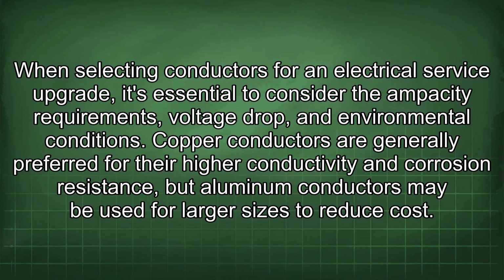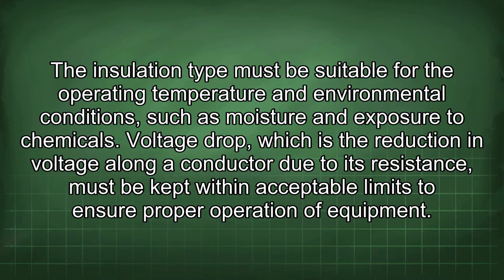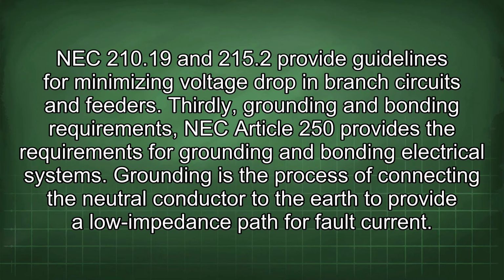Copper conductors are generally preferred for their higher conductivity and corrosion resistance, but aluminum conductors may be used for larger sizes to reduce cost. The insulation type must be suitable for the operating temperature and environmental conditions such as moisture and exposure to chemicals. Voltage drop, which is the reduction in voltage along a conductor due to its resistance, must be kept within acceptable limits to ensure proper operation of equipment. NEC 210.19 and 215.2 provide guidelines for minimizing voltage drop in branch circuits and feeders.